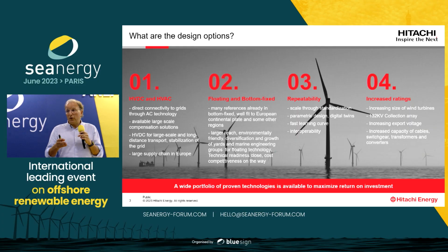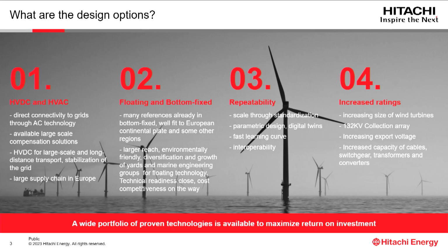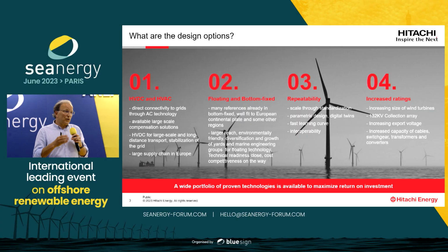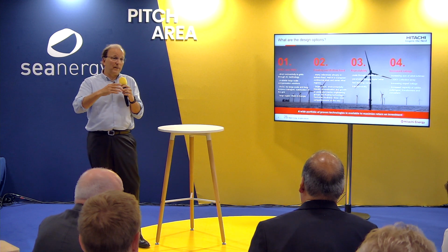Also good news is that because the space is wide and there's no real limitation in terms of visual impact or things like that, size matters. So we go to bigger and bigger projects and bigger turbines. You see the rating per turbine increasing, which is also an opportunity to switch to another voltage level, from 66 kV to 132 kV, saving on cable costs and on losses.